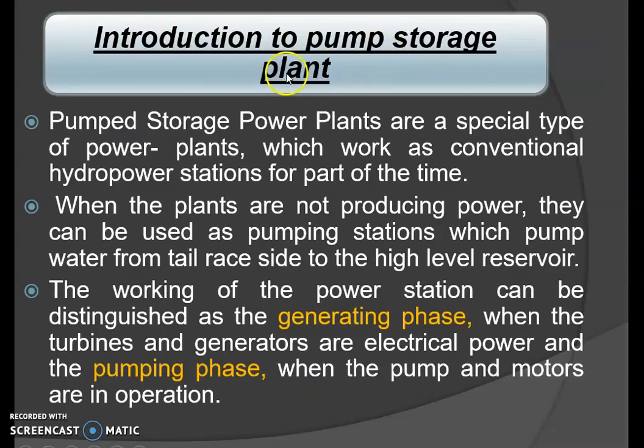Now, an introduction to pumped storage plants. Pumped storage power plants are a special type of power plant which work as a conventional hydropower station for part of the time. When the plants are not producing power, they can be used as pumping stations, which pump water from the tail race side to the high level reservoir. The working of the power station can be distinguished as the generating phase, when the turbines and generators produce electrical power, and the pumping phase, when the pumps and motors are in operation.